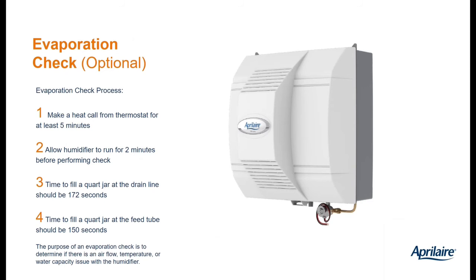Just want to give you some general recommendations. There is an evaporative capacity check. This is if you're stumped on troubleshooting. Always call tech support when you're on site; we'll be happy to help you. But this is something you can do as well. What this will do is confirm if the humidifier is evaporating the amount of water it's supposed to. If it is, the issue must be something external to the humidifier. The way it's installed doesn't let the humidifier run enough.